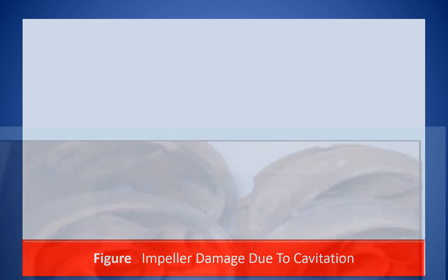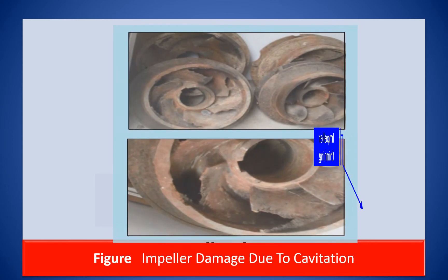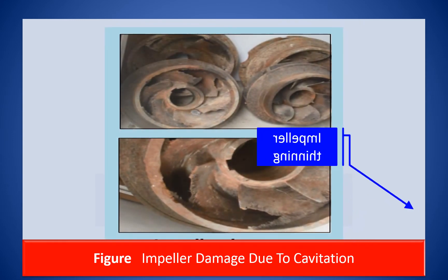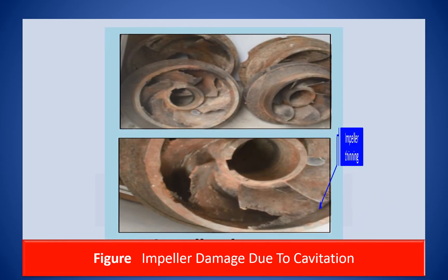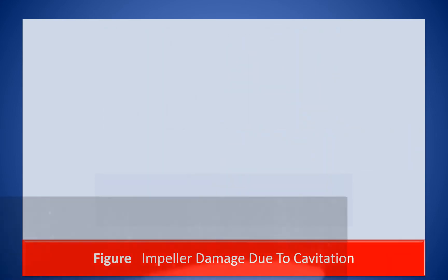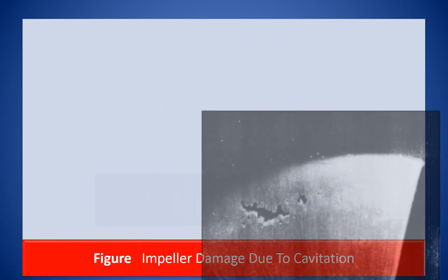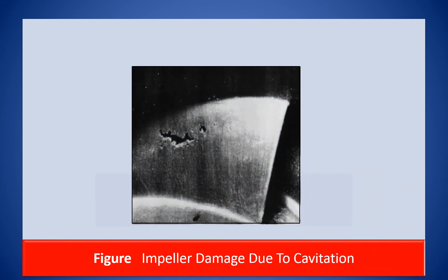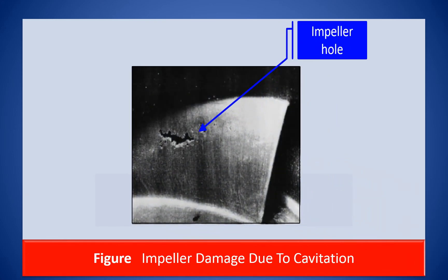This figure illustrates how cavitation causes thinning of the impeller vanes. This figure shows how a hole has formed on the impeller due to cavitation.